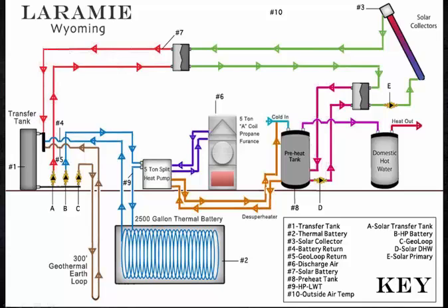But then we realized that by hooking it in series to the thermal battery and then allowing the controller to pump that B circuit that goes through the heat pump, whether or not the heat pump was running, that it would solve our problem. And so that's what we did, and it worked well. So now if, for example, the solar collectors are bringing BTUs in real time, they're going to be coming into the transfer tank.